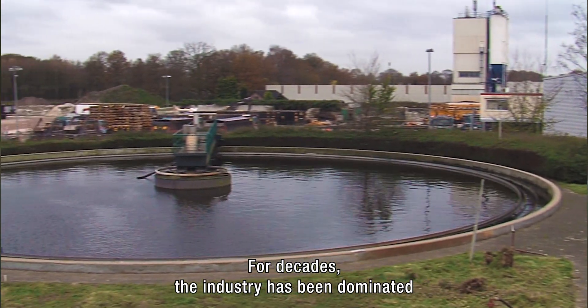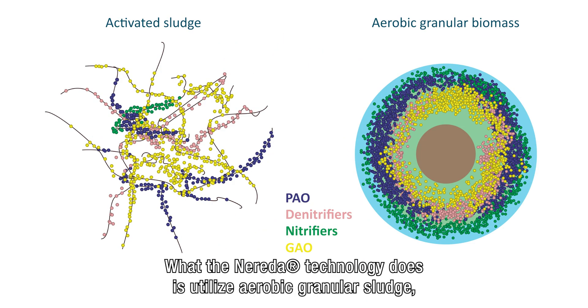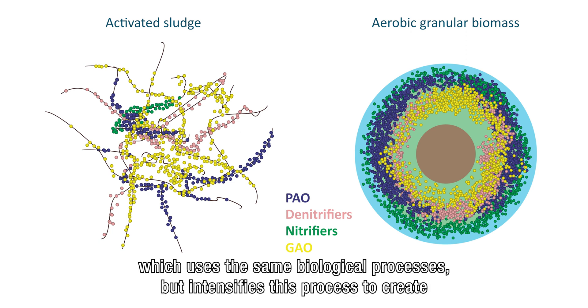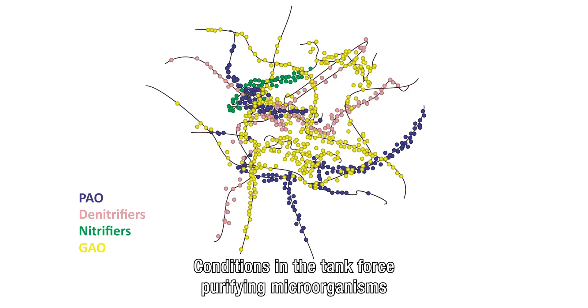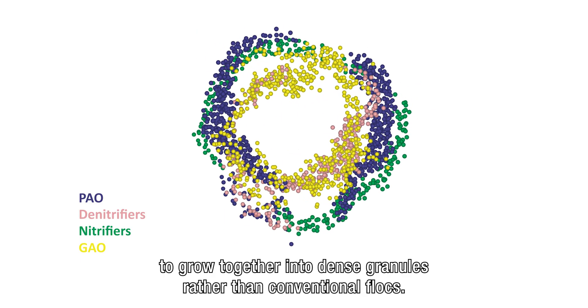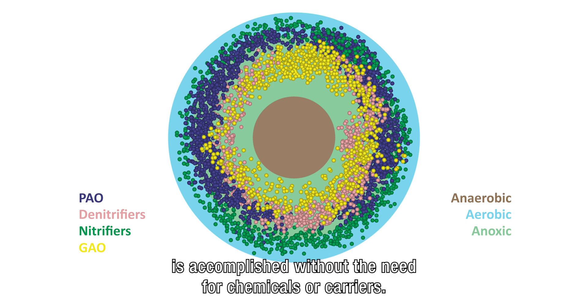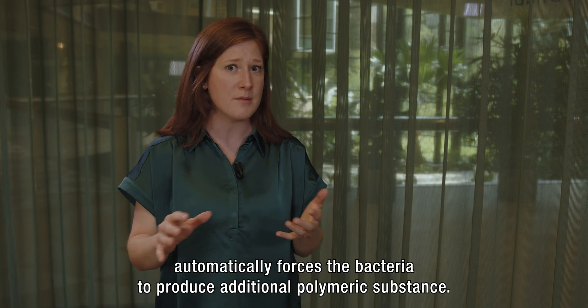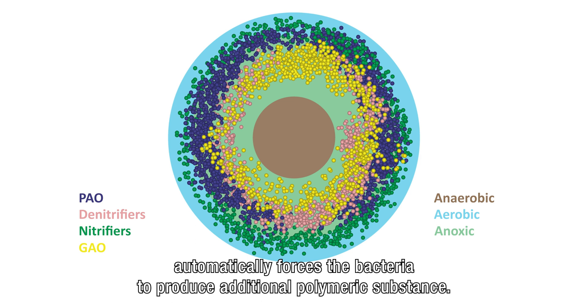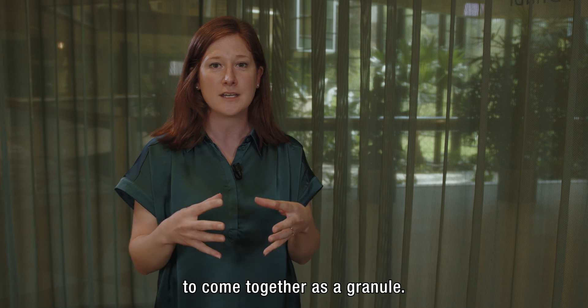For decades, the industry has been dominated by conventional activated sludge technologies. What the Nereda technology does is utilize aerobic granular sludge, which uses the same biological processes but intensifies them to create a setting where bacteria are forced to work harder and more efficiently. Conditions in the tank force purifying microorganisms to grow together into dense granules rather than conventional flocs. This process is accomplished without the need for chemicals or carriers. Rather, the optimized control of the process automatically forces the bacteria to produce additional polymeric substance, which then acts as a glue forcing the bacteria to come together as a granule.